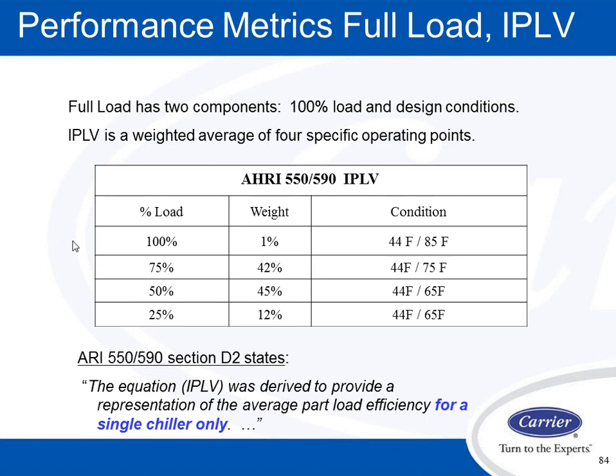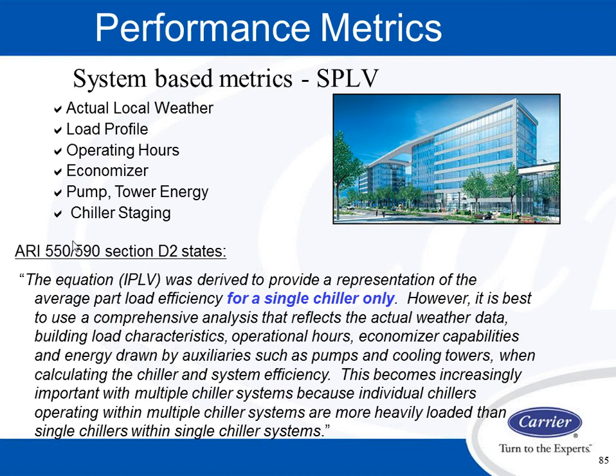IPLV is a way to rate a single chiller in a single plant, typically without an air side economizer. So the real way to measure chiller plant efficiency is what we call system part load value. We look at the actual load, local weather, the load profile, the operating hours, economizer, analyze the pump and the tower energy, and look at the chiller staging. Again, the IPLV was derived from a representation of an average part load for a single chiller. We need to look at all those other options when we're analyzing a chiller plant and look at system part load value.